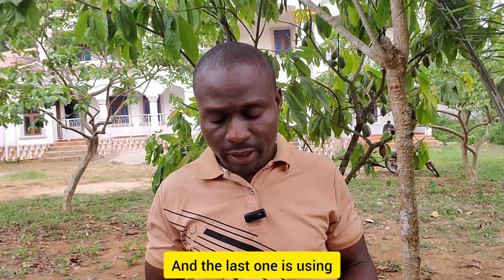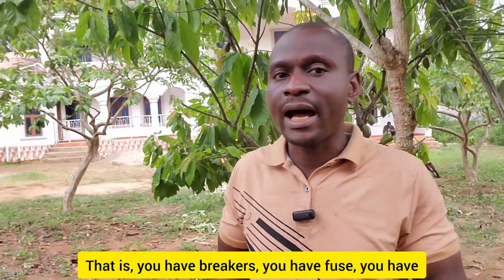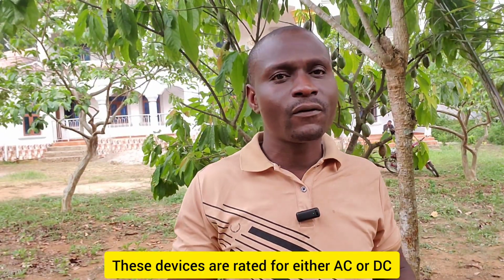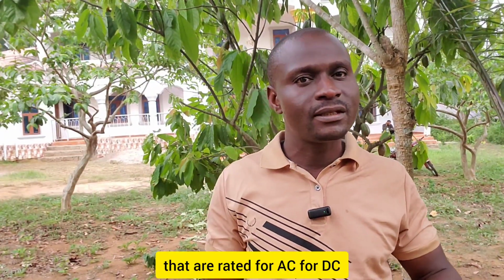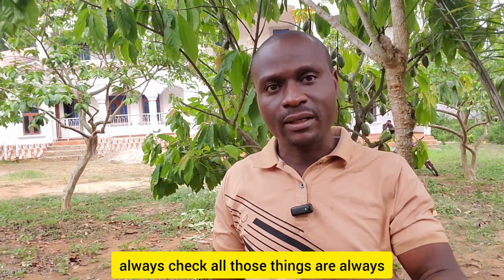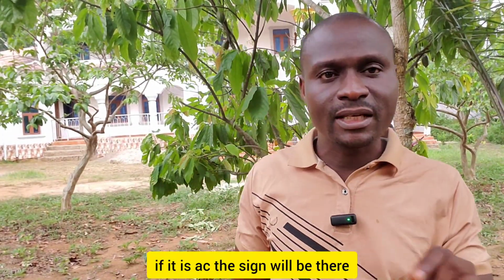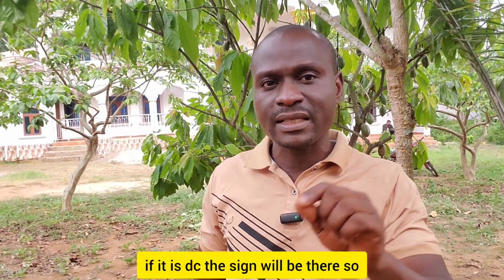And the last one is using AC OCPDs for DC. That is, you have breakers, you have fuses, you have such protective devices. These devices are rated for either AC or DC. Don't use the ones that are rated for AC for DC. Always check. All those things are written there. If it is AC, the sign will be there. If it is DC, the sign will be there.